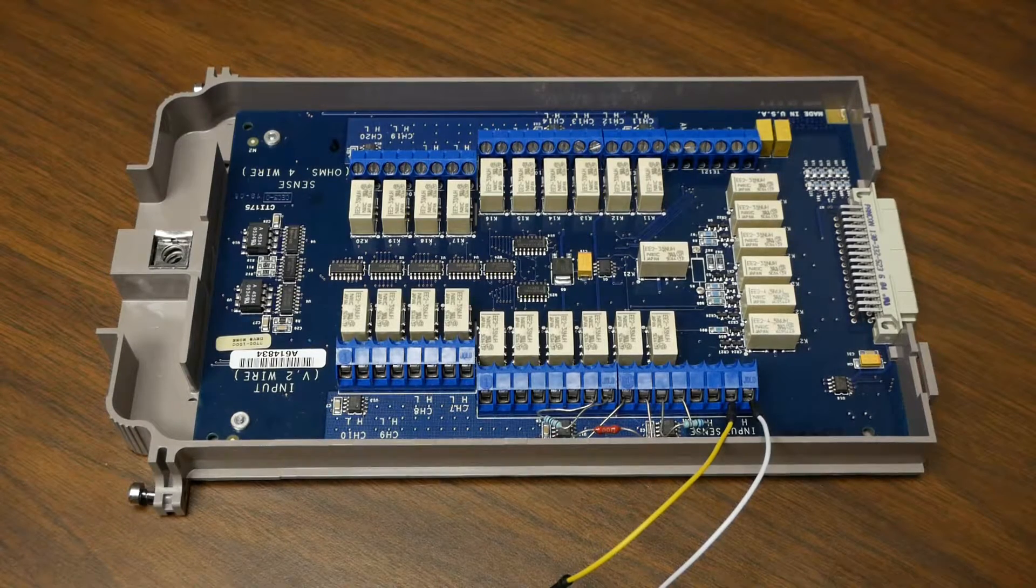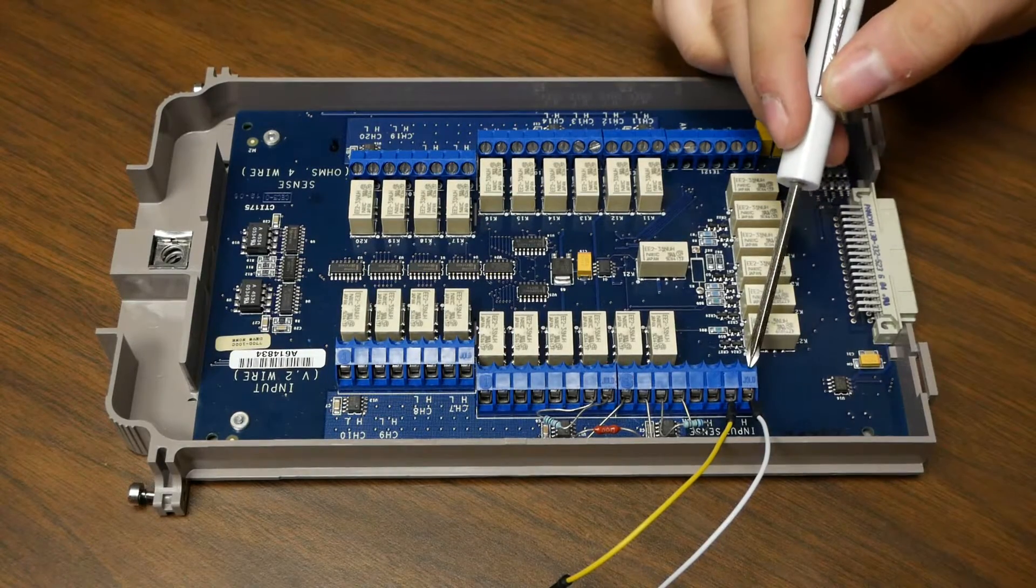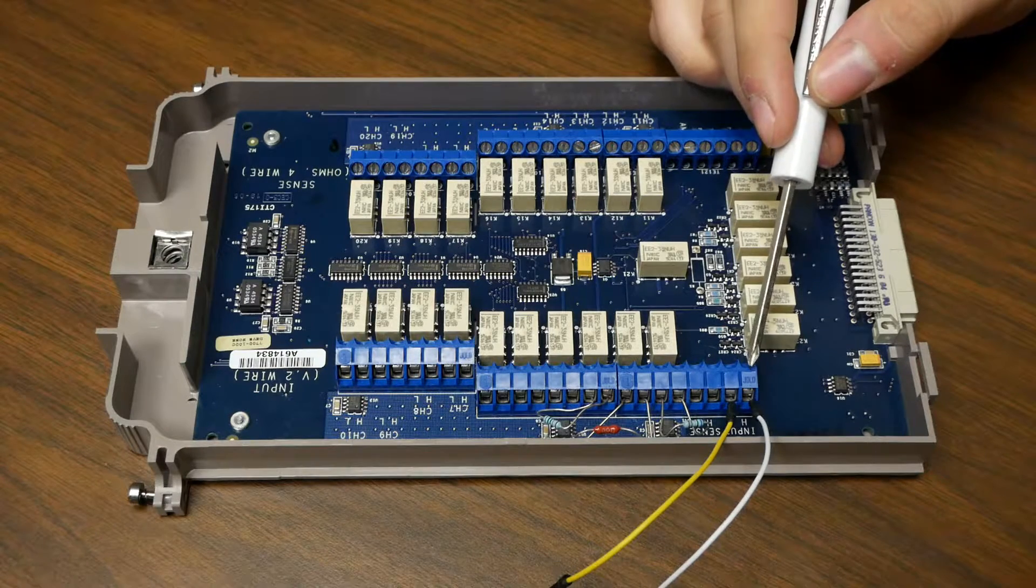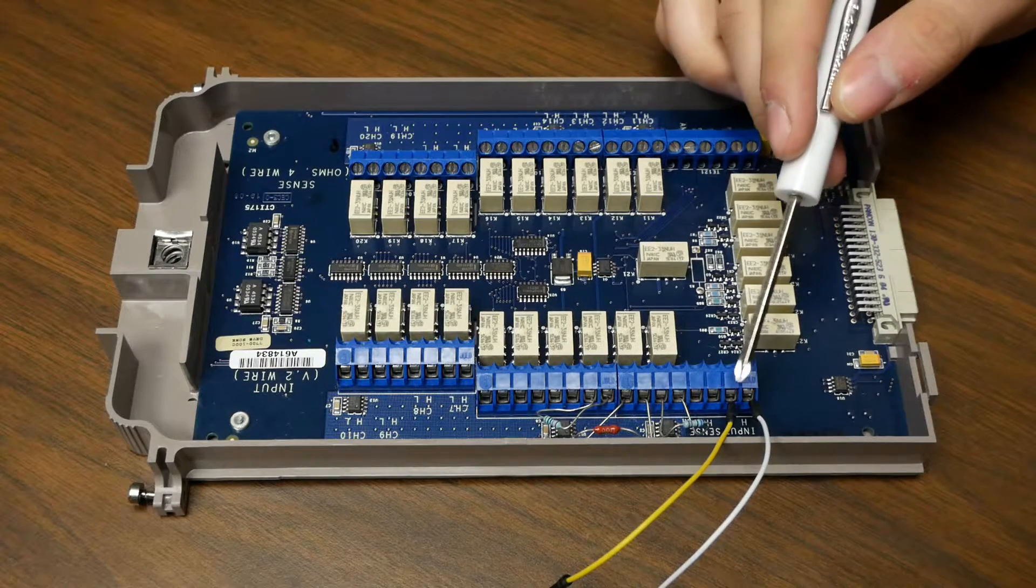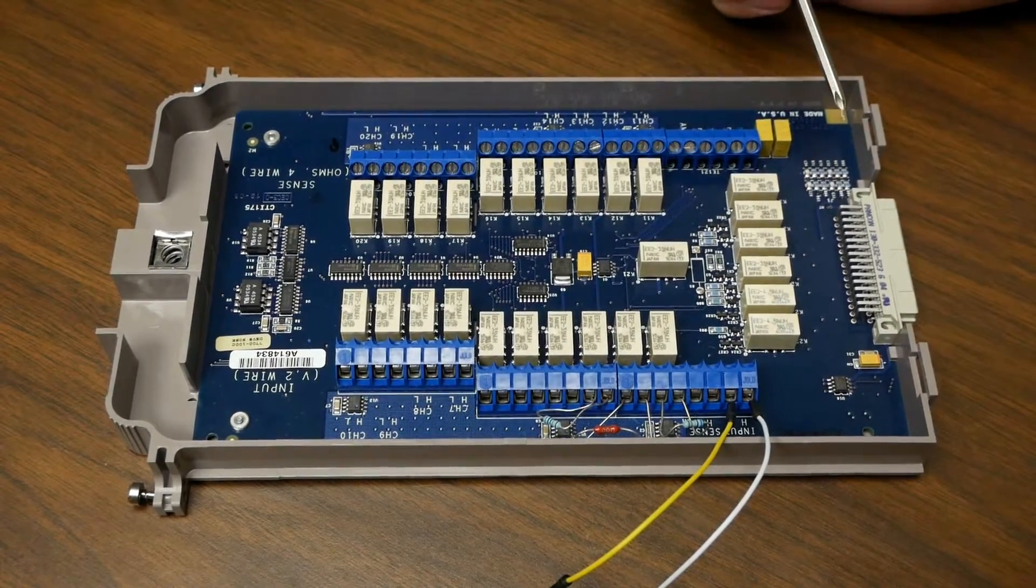Now we're going to configure our 7700 switch card. We'll connect our external instrument, in this case our model 2470 SMU, to the input high and low. This will then run from our jumpers outside of the back of the card and out to our external instrument.